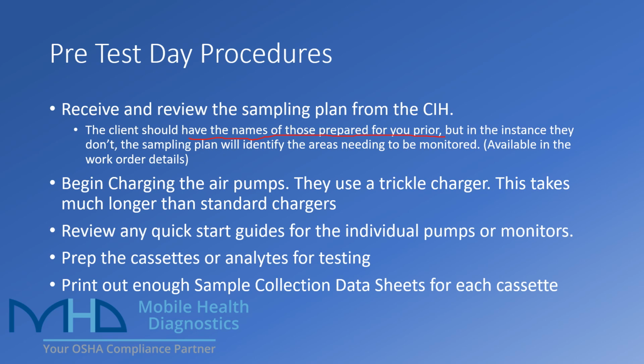You're also going to want to make sure that you start charging the air pumps. Like we just talked about, those are trickle chargers. They take significantly longer. They are supposed to come pre-charged. SGS Galson's direct statement on that is the pumps should be fine so long as they're used within 48 hours of the shipping date where the equipment was sent. But it's always better to be cautious. So as soon as you get the equipment, you're going to want to remove those pumps and start them charging on those trickle chargers. You should also review any of the quick start guides that came with the equipment and familiarize yourself with the different collection mediums that are being sent to you.